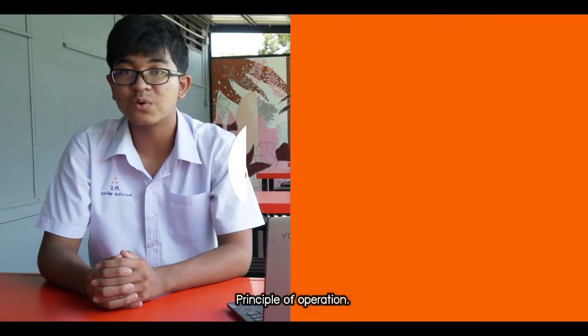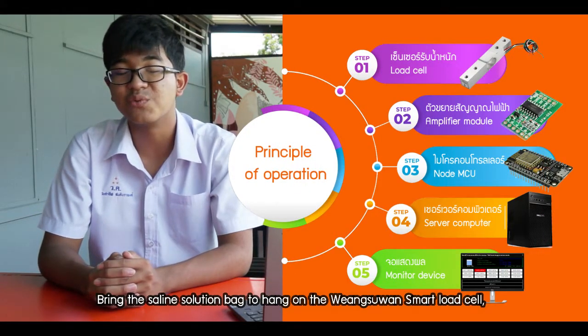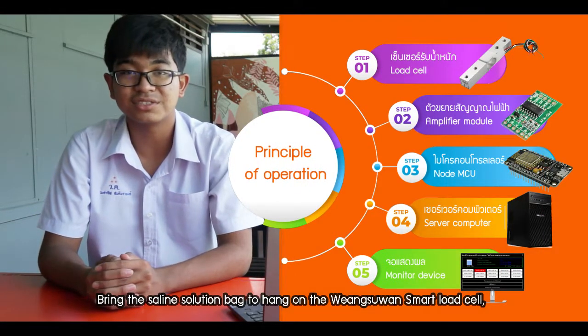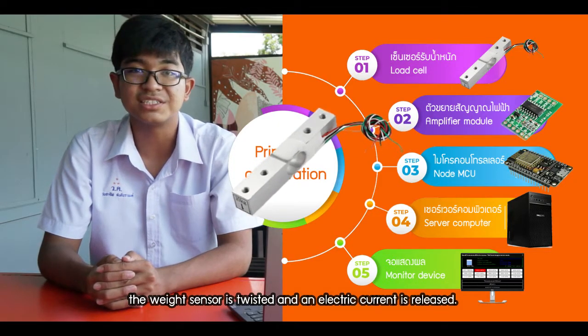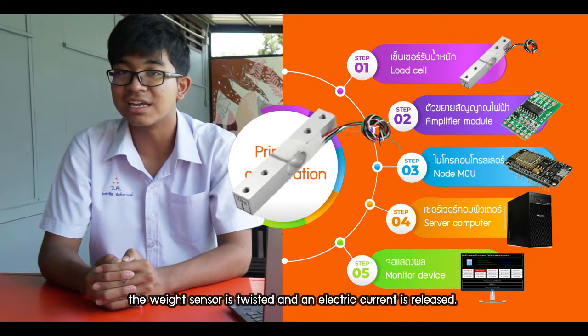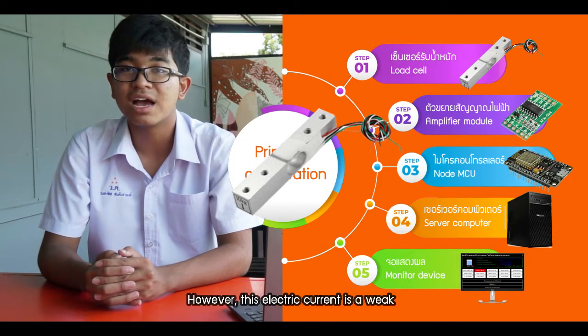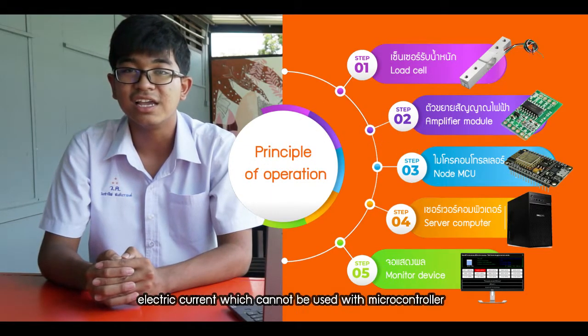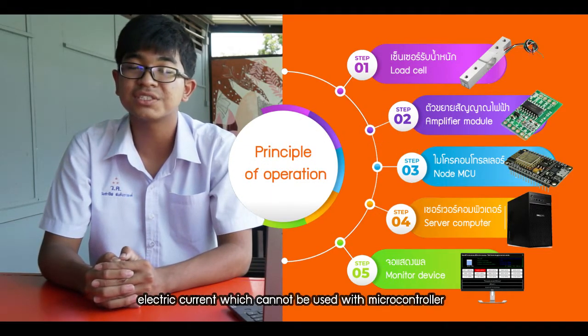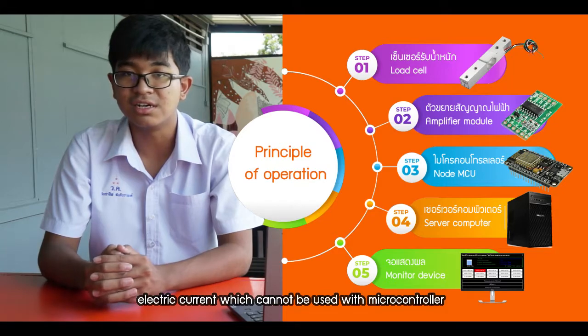The principle of operation: the saline solution bag is hung on the device's small load cell sensor. When weight is applied to the sensor, an electric current is released. However, this electric current is weak and cannot be used directly with a microcontroller.